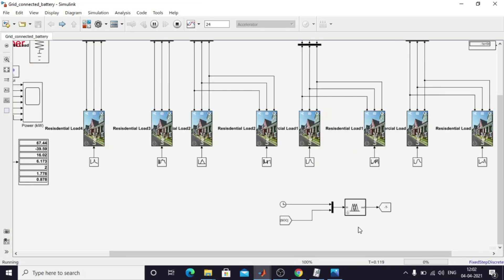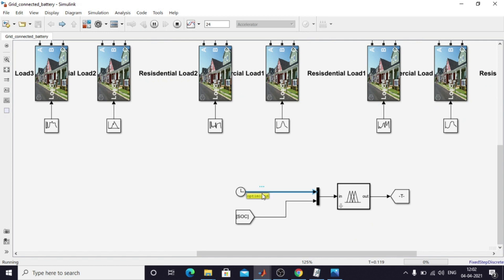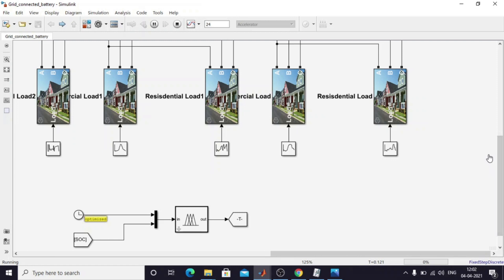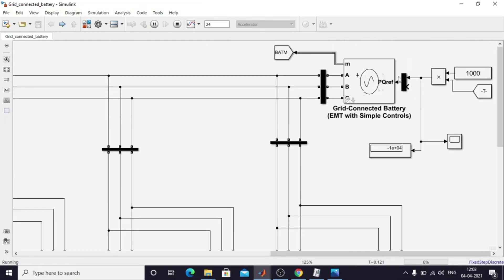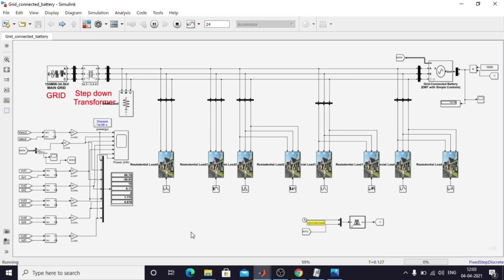The fuzzy logic controller receives two inputs: time and SOC of the battery. Based on these it generates a command that controls the power reference of the battery — the PQ reference. If the sign is negative, for example minus 10 kilowatt, the battery goes into charging mode. The command varies based on time of day and SOC, resulting in charging, discharging, or idle conditions.